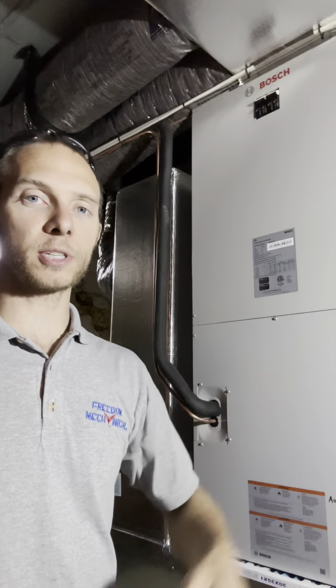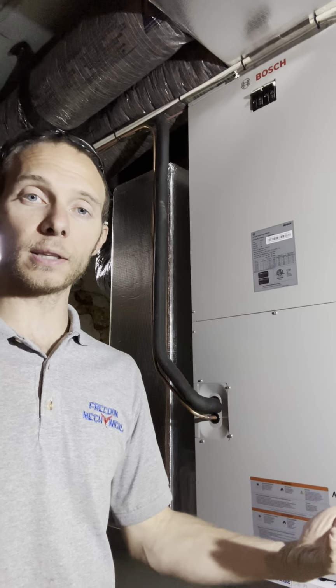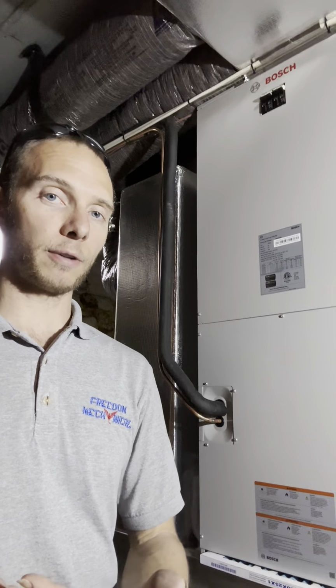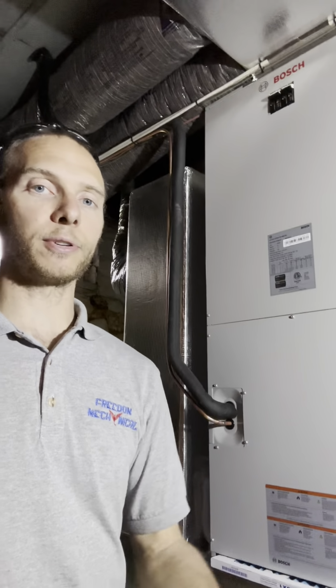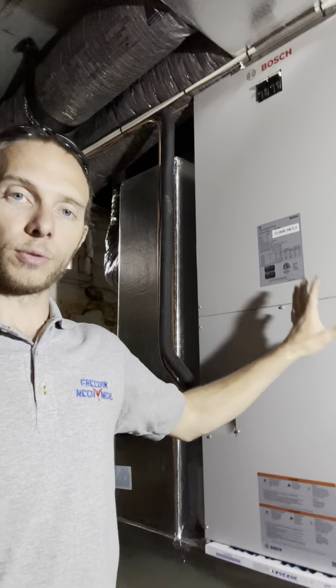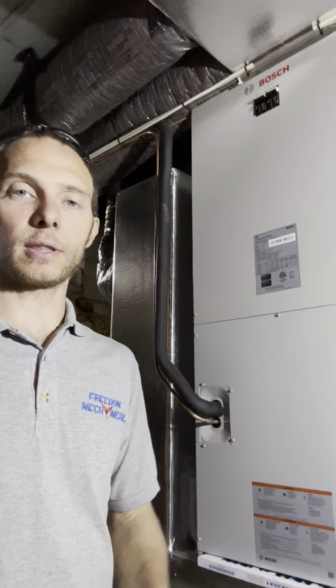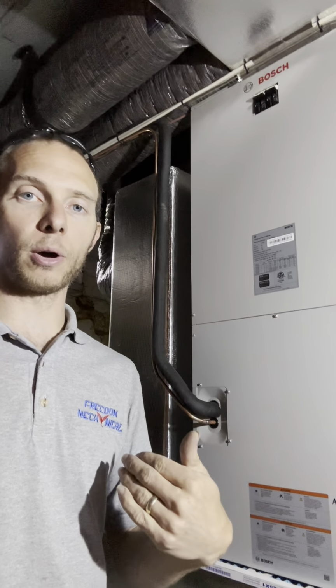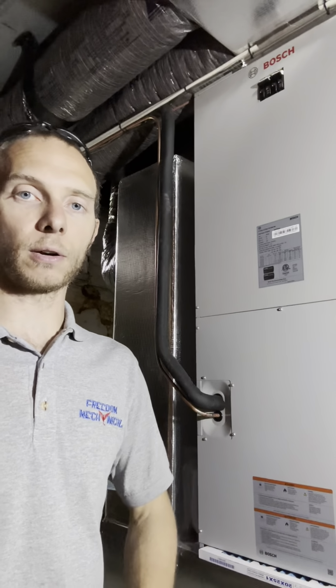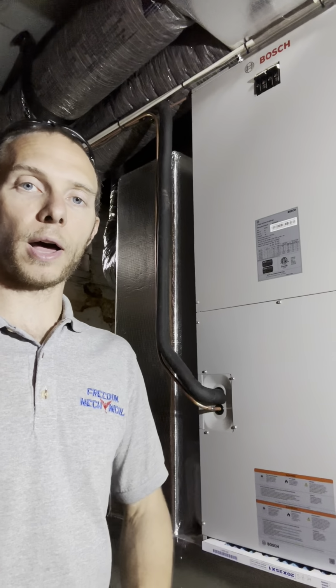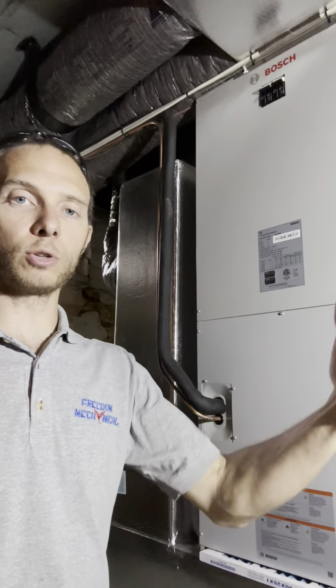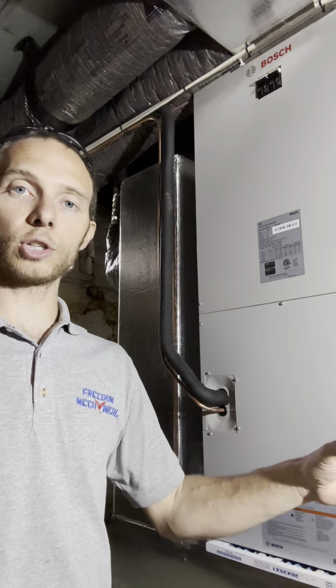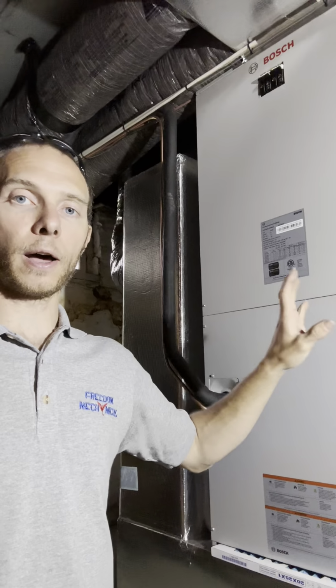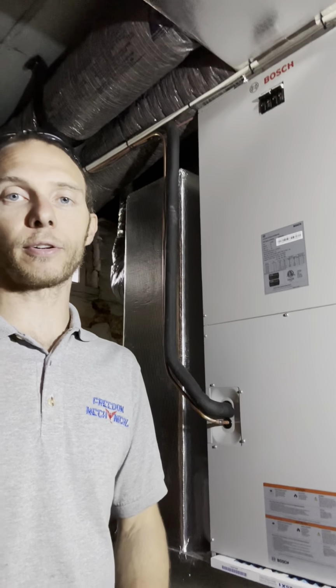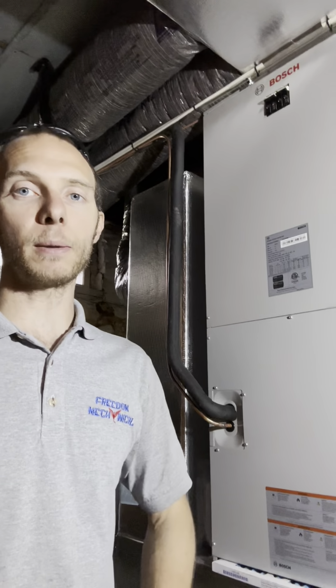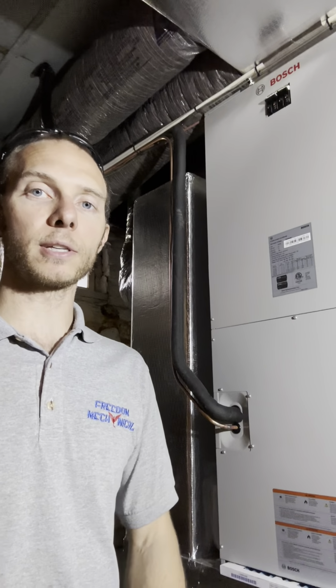When the thermostat calls for heat, if it brings the blower on immediately, the outdoor unit has not built up enough heat yet in the coil to actually make it feel warm. So you're going to get a shot of cold air. So this 2.0 air handler has the ability to hold off the blower until it sees 90 degrees in here on a sensor. The entry-level light air handler does not have that, so when you call for heat at the thermostat, unless your technician has installed an aftermarket control, you're going to have a shot of cold air for the first 3 minutes before that outdoor heat pump begins to rev up. So that's something to pay attention to.